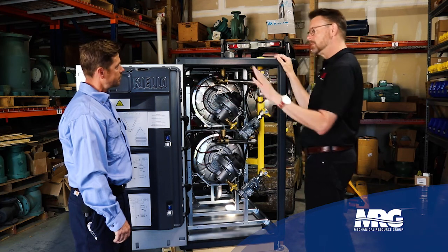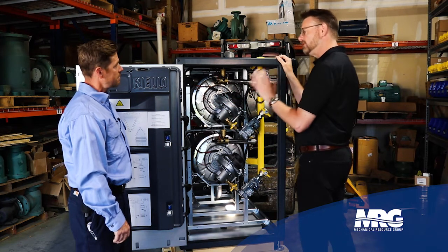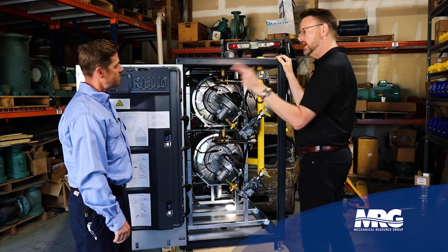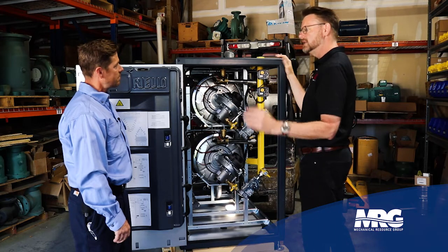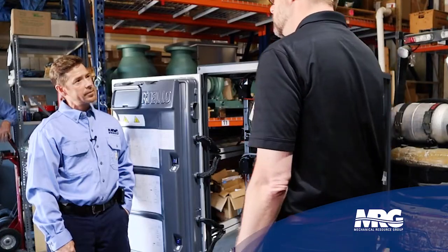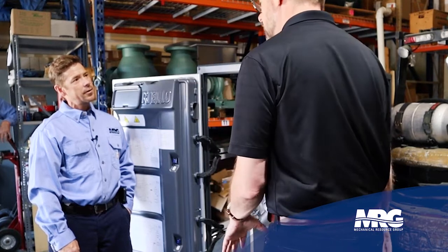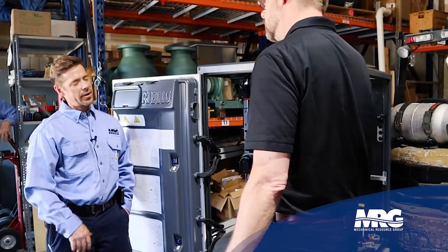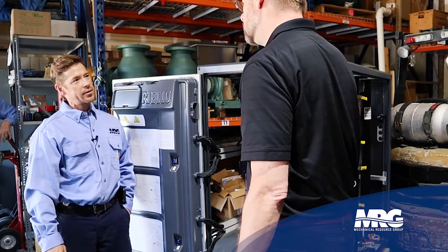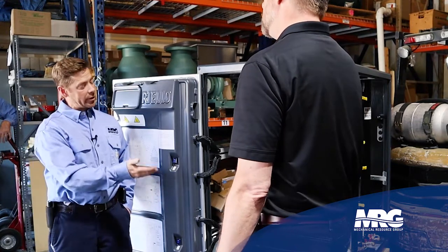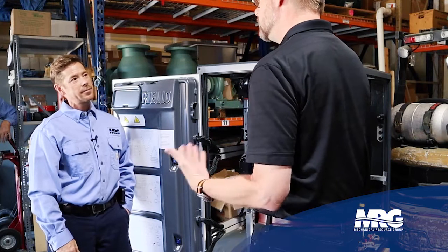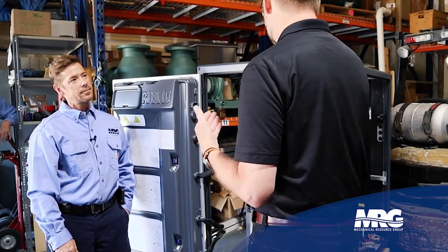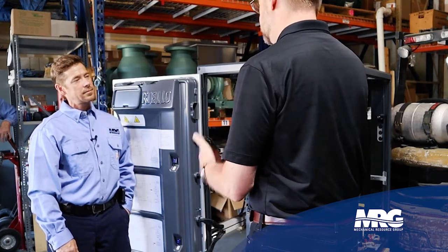Right. How much capacity was available with that fired heat exchanger, that boiler, when that ignition problem occurred? How much capacity did it have out of that box? 2 million BTUs, and it was down, all 2 million BTUs. Right. It had actually two heat exchangers, and because one failed, it completely shut. Oh, it didn't have redundancy. It didn't have redundancy, so it was a dual heat exchanger system. However, the failure of one caused the failure of both.